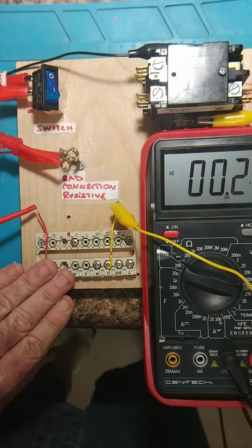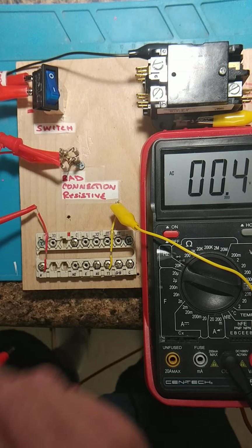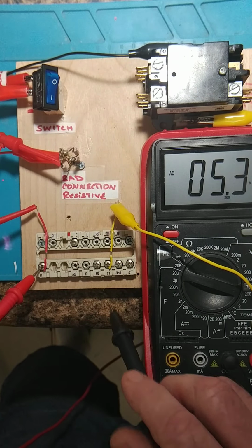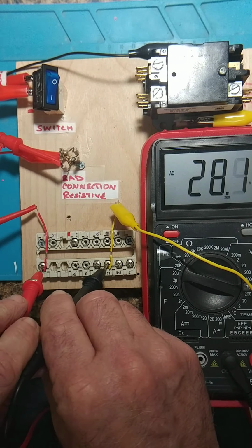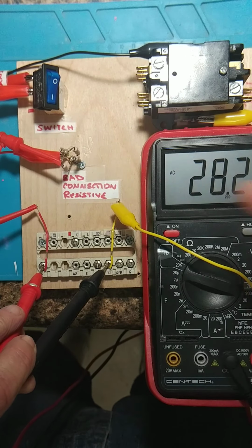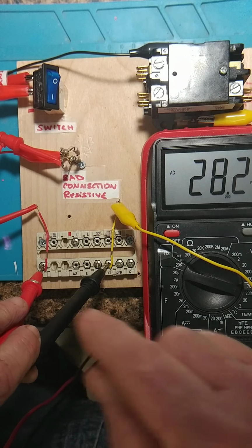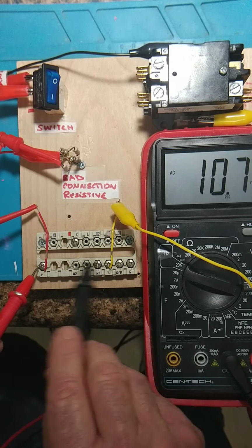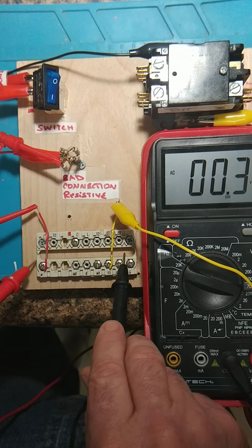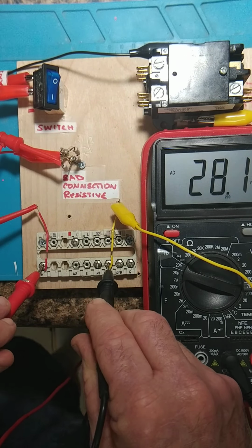Now right now my thermostat's open. So what I want to show you is that I've got 24 volts on. I'm going to flip my switch on. And notice I've got 28 volts. But I've got a resistive connection here. So shouldn't I be dropping voltage across that bad connection? No, because there's no current. The circuit's open because my thermostat is not calling. My thermostat's off the sub base and it's open. So I'm going to read that. Everything looks normal. I don't see a problem here.